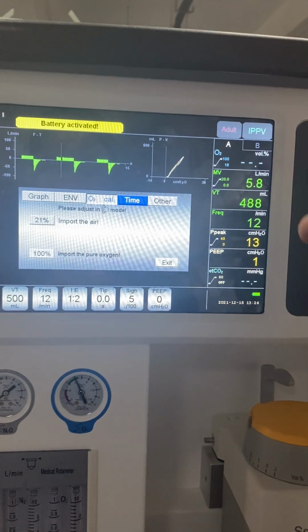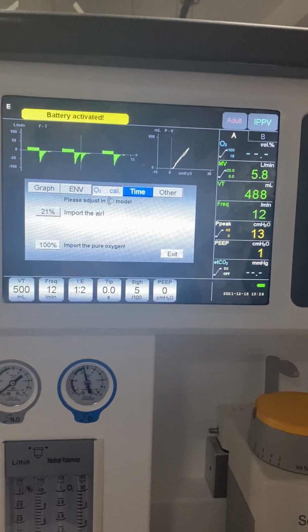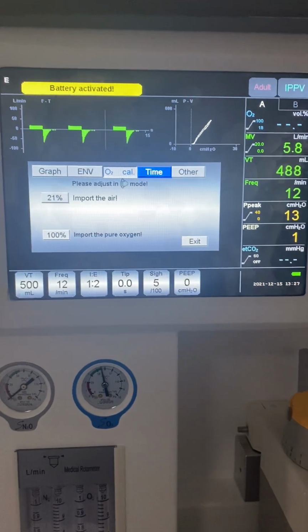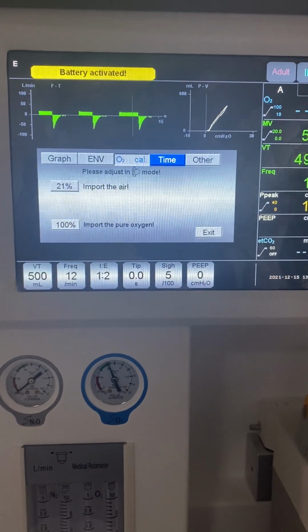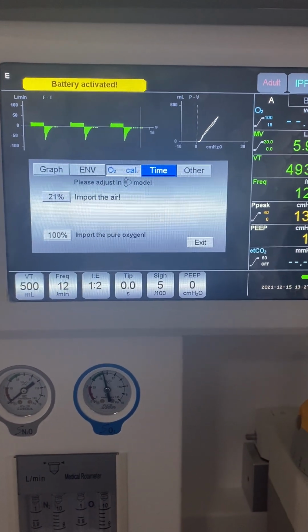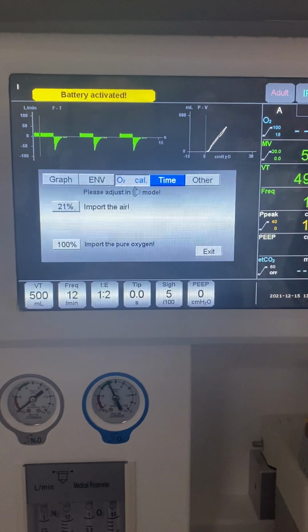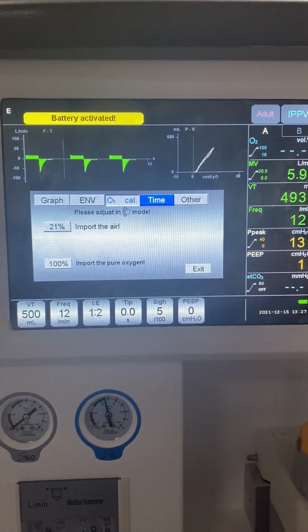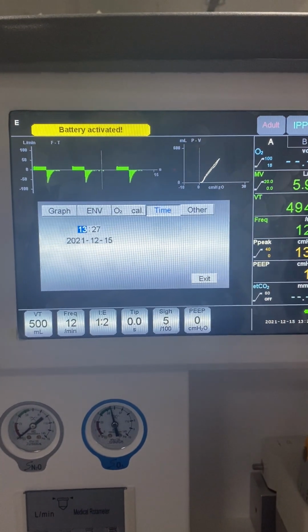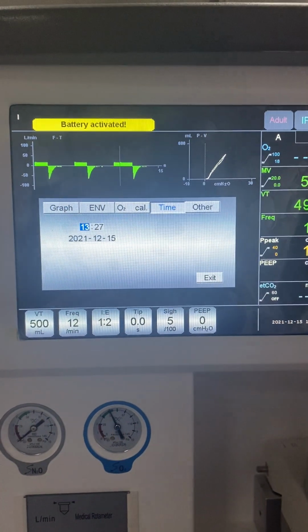Also, there is another situation where you need to use this oxygen calibration. For example, if the oxygen sensor, after 1 year or 1.5 years, has worn out, you need to change to a new oxygen sensor. And after the change, we need to do it again. So only these two situations need it. The fourth column here will be the time setting. It's just like your mobile phone, to set the time to your local time.